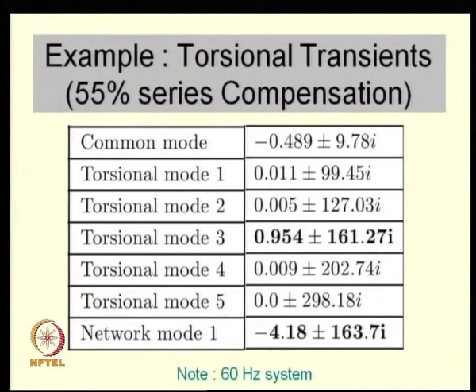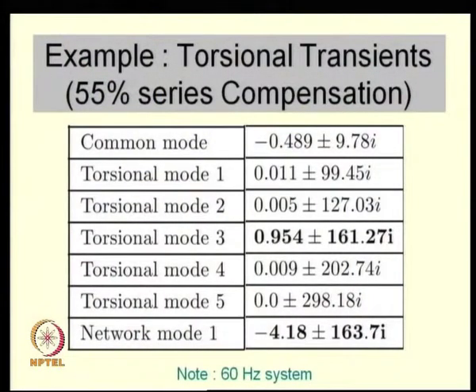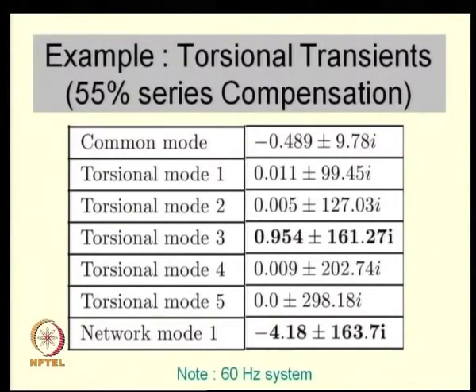There are further qualifications: it is assumed the electrical torque can affect all torsional modes, but this need not be true. The electrical torque is applied at the generator mass and may not affect all torsional modes equally. In this system, torsional mode 5 is hardly affected by the sub-synchronous network mode. The extent to which electrical torque affects a particular mode depends on the system, and this analysis can be done using eigenvalue and eigenvector analysis.